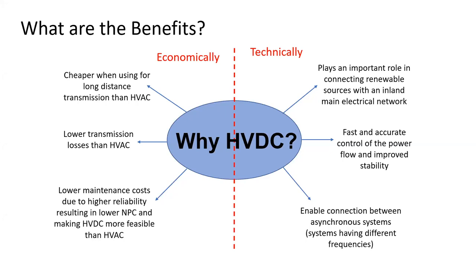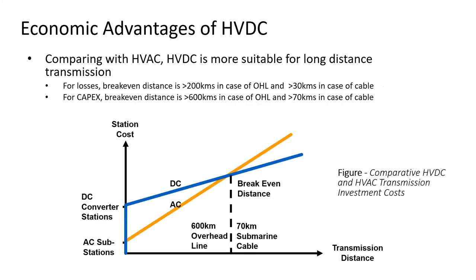And HVDC is the only technology, so this is not a point of comparison between two technologies. HVDC is the only technology that can be used to connect asynchronous systems with different frequency, like a 50 hertz system with a 60 hertz system. Under economic benefits, I said HVDC is cheaper than HVAC over long distance. But what is that distance?